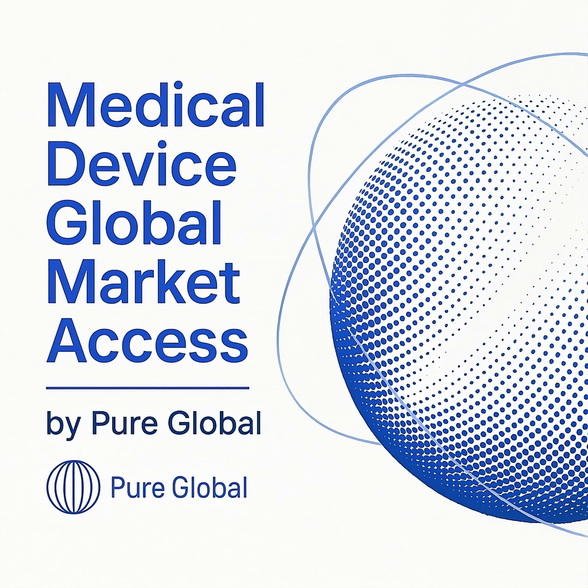Class 3 devices are the highest risk, often supporting or sustaining life. They require a comprehensive pre-market approval, or PMA, application with extensive clinical data. Pacemakers and heart valves fall into this category.